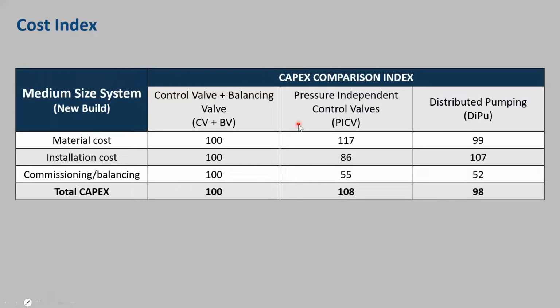So simply taking out those older style control and balancing valves and replacing them with pressure independent control valves, you're going to see a very significant increase in upfront material costs. The pressure independent control valves cost more than an older style valve. The installation cost is going to be a little easier, because remember, that pressure independent control valve is a 3-in-1 valve. So you've got one valve to install as opposed to 2 or 3 different devices. And lastly, the commissioning and balancing of that is going to be a little bit easier, at least dependent on system type, compared to the index.